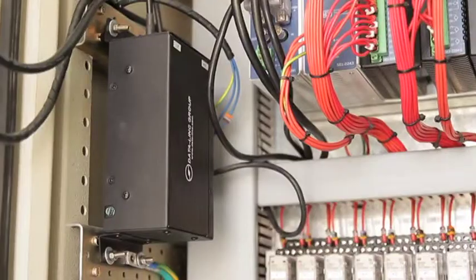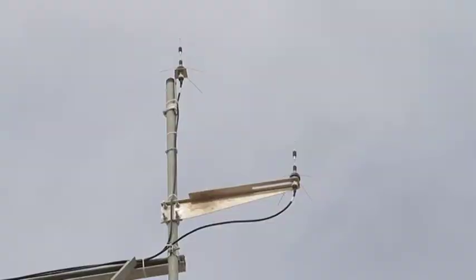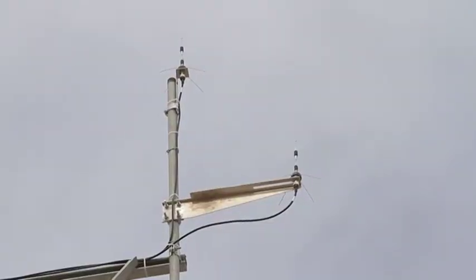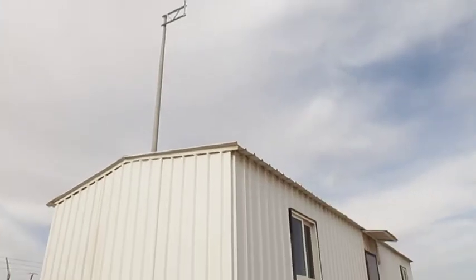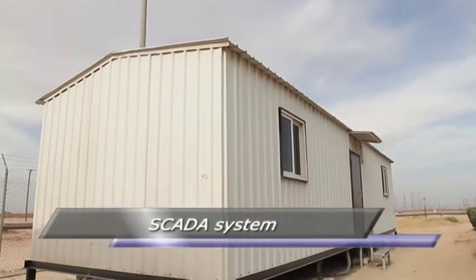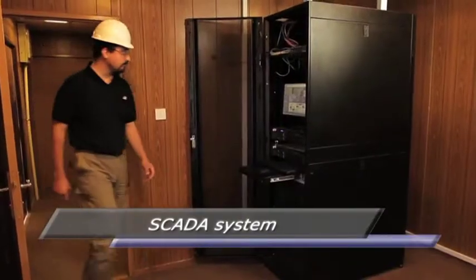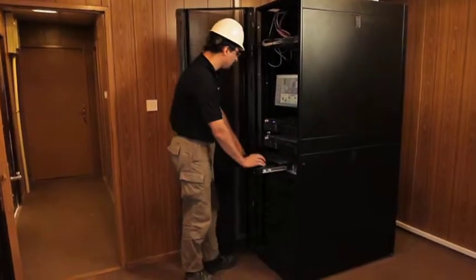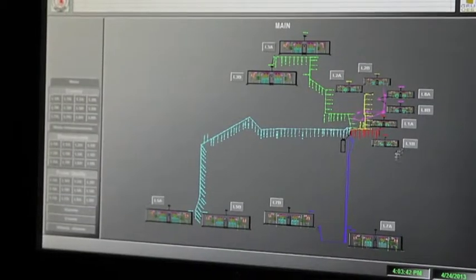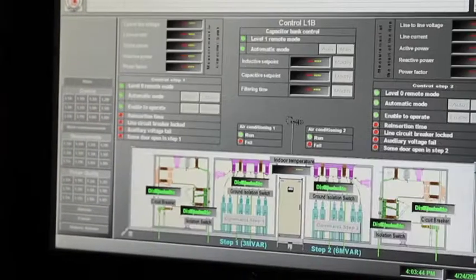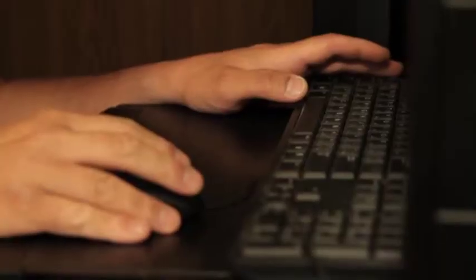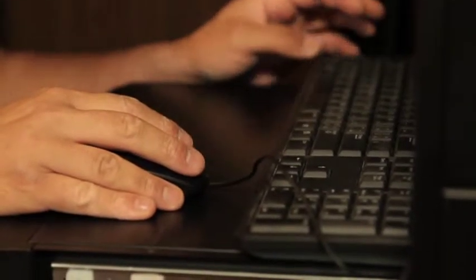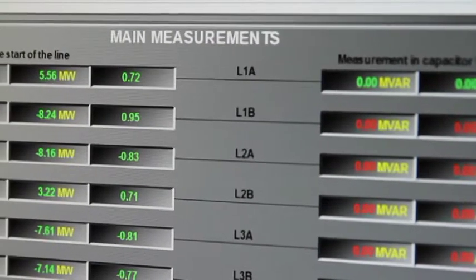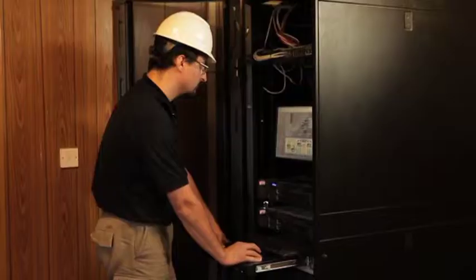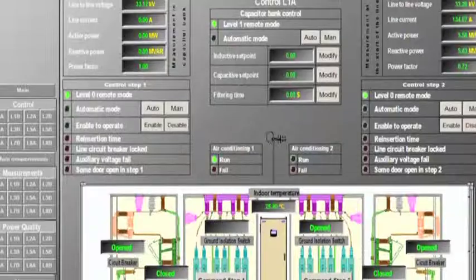Local control panels of harmonic filter banks positioned throughout the oil field are connected by a radio link to a SCADA system in a central control room. The SCADA system allows remote monitoring of all filter variables, which are represented graphically in a mimic diagram on the central control panel screen. The control system also carries a historical log of operation events and protection tripping.